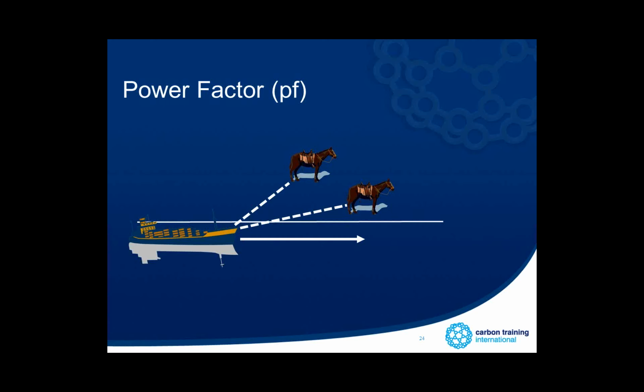But if you've got a power factor of 0.8, and even really now below 0.9, it's power factor correction, which is an installation that occurs at your meter, that has a payback typically of 18 months or less in most cases. So where you've got a poor power factor, it can be well worth addressing. And the typical things you're looking for are lots of electric motors, or large banks of fluorescent lighting and things like that, which will typically give you a poor power factor.